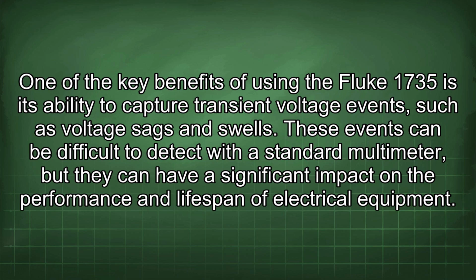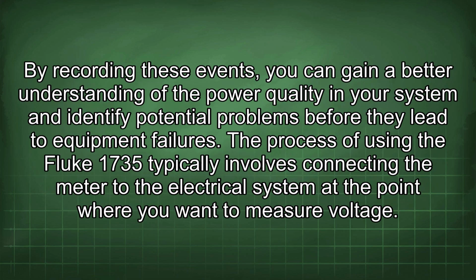One of the key benefits of using the Fluke 1735 is its ability to capture transient voltage events, such as voltage sags and swells. These events can be difficult to detect with a standard multimeter, but they can have a significant impact on the performance and lifespan of electrical equipment. By recording these events, you can gain a better understanding of the power quality in your system and identify potential problems before they lead to equipment failures.